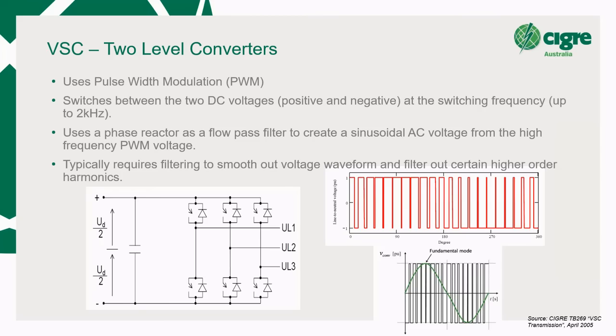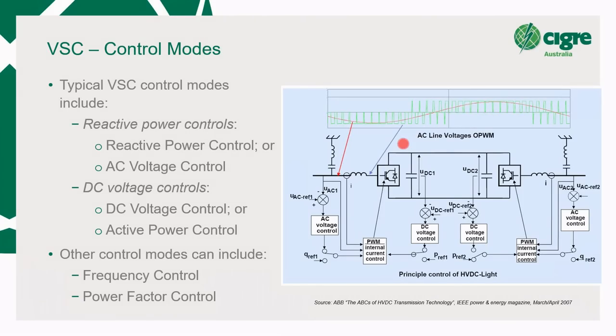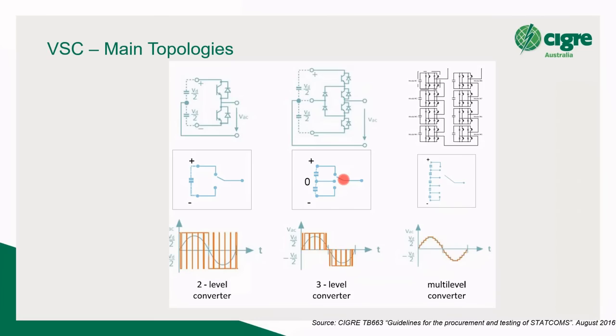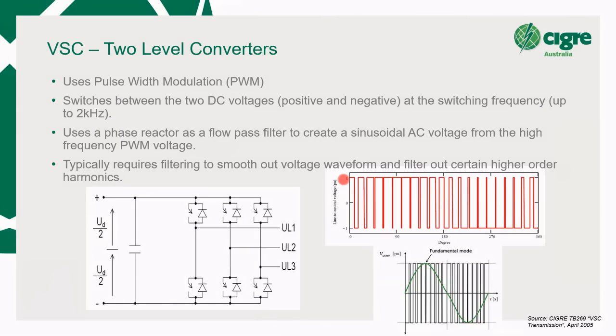It uses a phase reactor as a low pass filter to create the sinusoidal AC voltage from the high frequency pulse width modulation voltage. So it goes from this type of waveform, and you can see it pulls out the fundamental mode. It's usually quite noisy at this point, so you need a fair amount of AC filtering to get that. This diagram here also shows what the waveform looks like outside the converter and what it looks like more or less after you've gone through the phase reactor and after you've gone through the AC filters. So that's the two level.